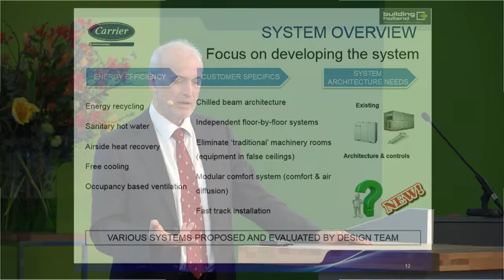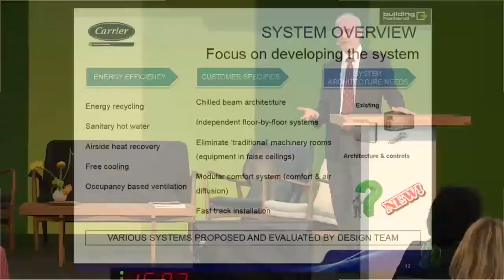So with that as a background, we were now in a situation where we knew how to improve the energy efficiency in terms of system design. We knew the areas to improve upon: sanitary hot water use, free cooling, airside heat recovery, and we wanted to better manage the occupancy ventilation. Now, I just remind you, the customer had some constraints for us. He wanted a chilled beam type of system, a hydronic system. He wanted a floor-by-floor approach to that building. He wanted to eliminate traditional plant rooms in order to gain more rental space. And, as I mentioned, he still wanted a modular comfort approach to that system.